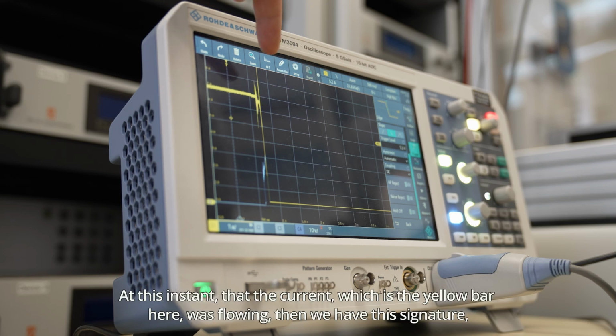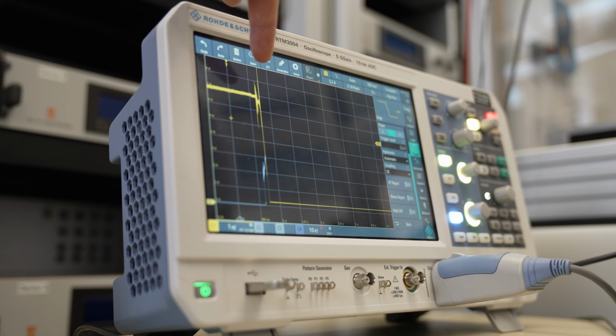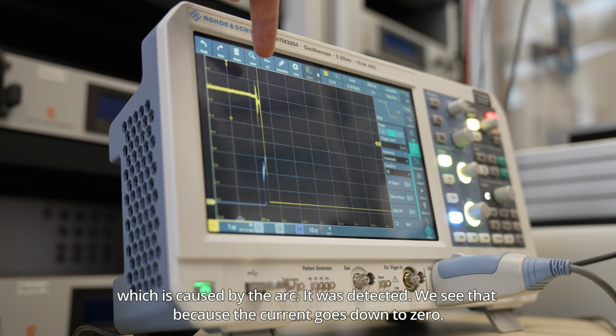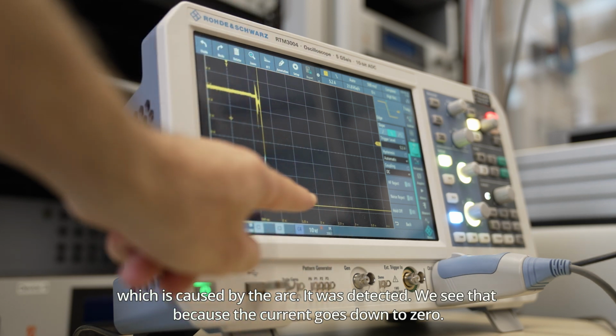At this instant, the current, which is the yellow bar here, was flowing. Then we have this signature, which is caused by the arc. It was detected. We see that because the current goes down to 0.